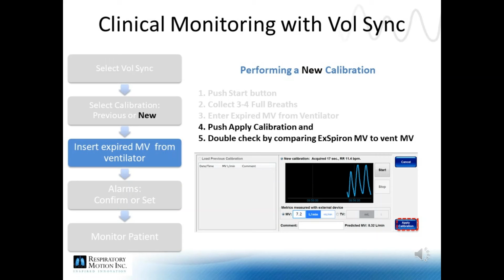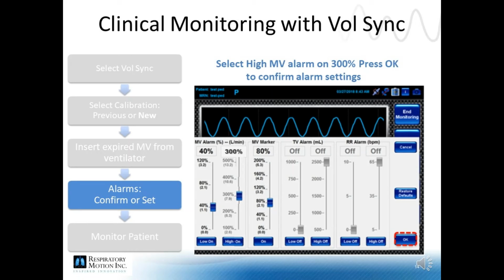Once you have entered expired minute ventilation, verify the ventilator and the ExSpiron both have approximately the same values for minute ventilation, tidal volume, and respiratory rate. Occasionally, if there was a problem with the synchronization, they may show greater than a 1 liter per minute variance. If so, you should consider repeating the volume sync procedure. Once you are satisfied with the synchronization values, select Apply Calibration.